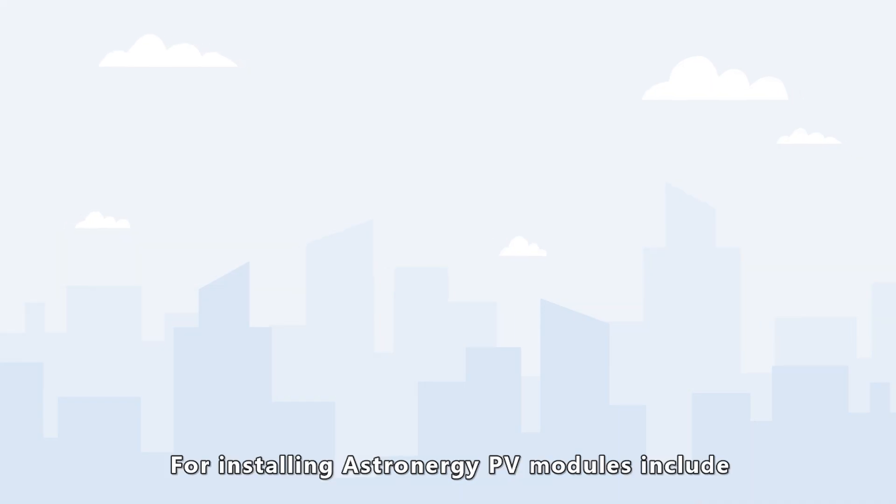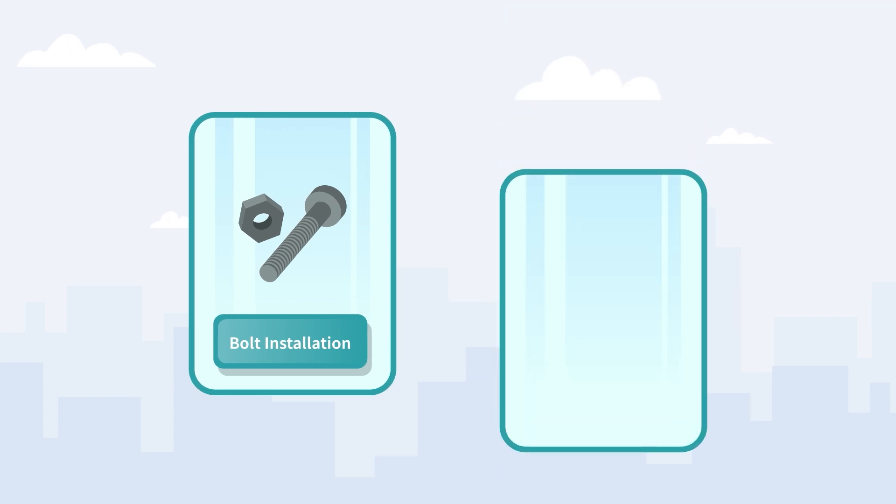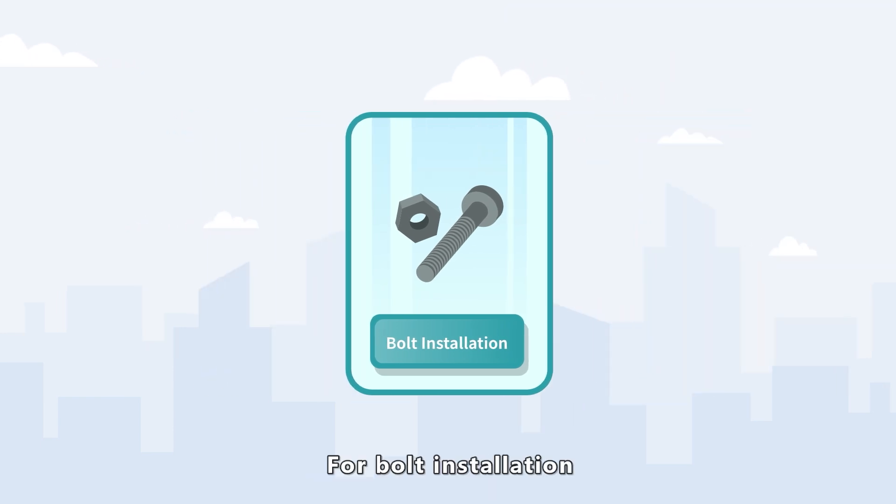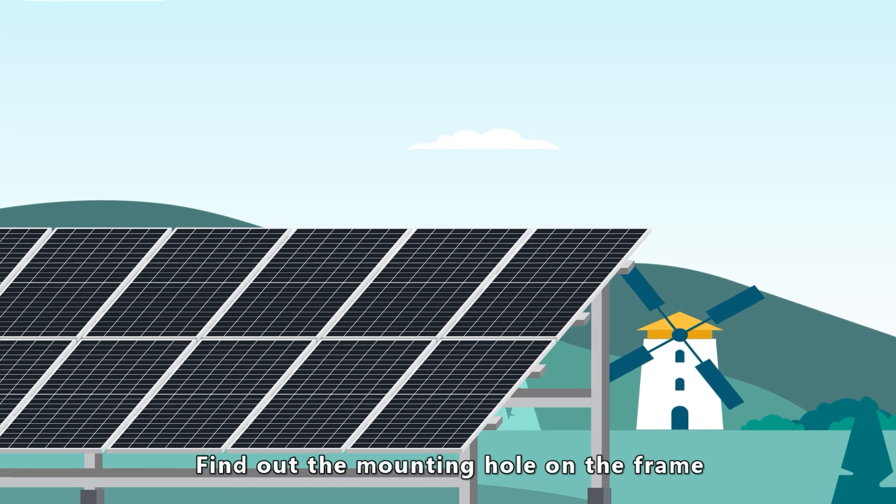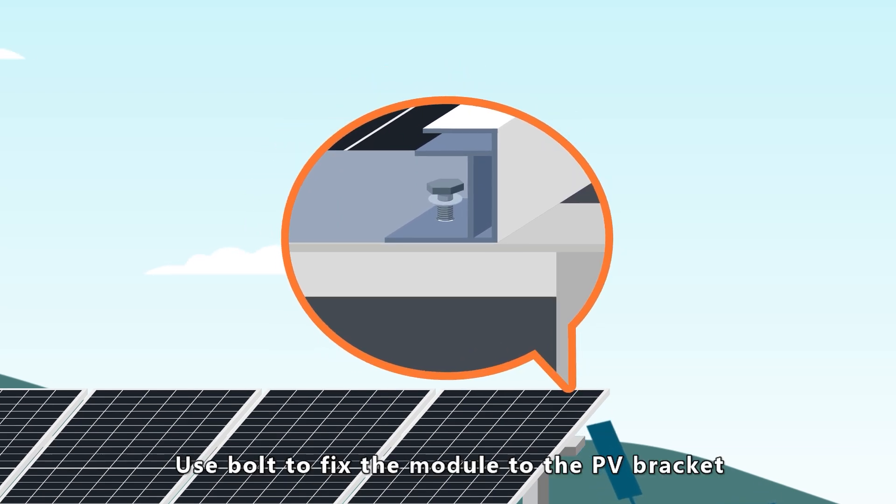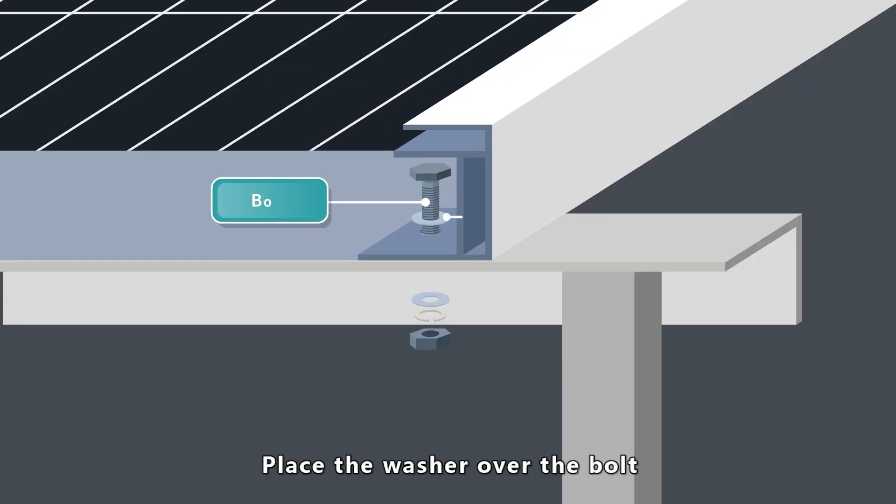Common methods for installing Astronergy PV modules include bolt installation and clamp installation. For bolt installation, find out the mounting hole on the frame. Use the bolt to fix the module to the PV bracket. Place the washer over the bolt.